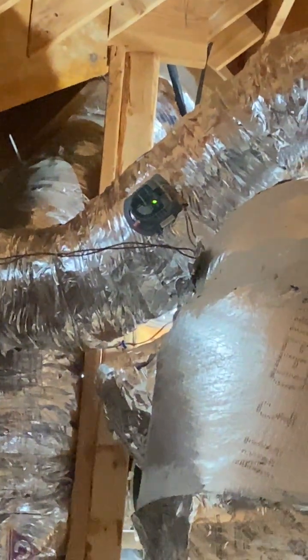Down here, let's see, actually around over here. Again, zone control valves are not difficult to put in. You should properly label everything. Here is the zone control valve up here for zone 3. You can see the duct comes off of the main and goes over that way. And there is the control valve for it. And it is a Lennox style, and it's currently showing green, which means it's open. I have no heat demand from any zone at this particular point. So I got 3 zones.